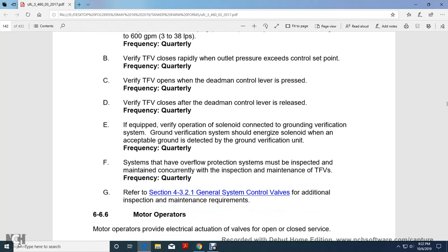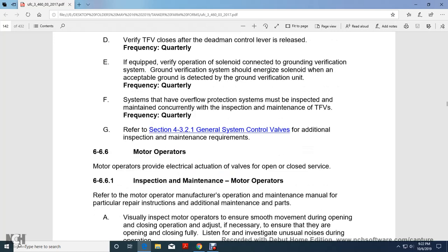If equipped, verify the operation of the solenoid connected with the ground verification system. The ground verification unit should energize the solenoid when an acceptable ground is detected. The frequency is quarterly. The overflow protection system must be inspected with the current maintenance inspection. Maintain the truck fill valves quarterly. Refer to section 4321, general system control valves, additional inspection, maintenance and requirements.